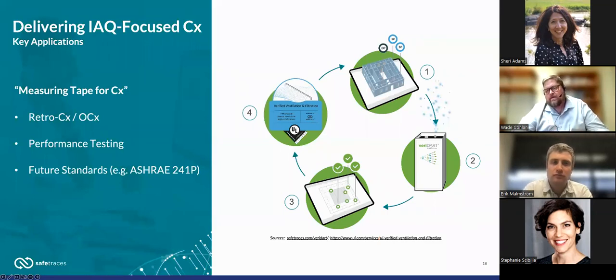I can do an integrity test on filters. I can confirm I've got the right amount of outdoor air via a certified TAB technician doing the TAB work with certified, calibrated equipment. But then, how does the overall system perform?